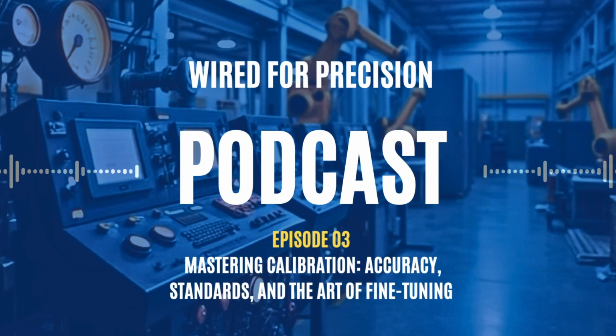Loop calibrators. These are designed specifically for current loops, often used in analog process signals, 4 to 20 milliamps. They can simulate, source, and measure loop current, making them indispensable for control loops. Each method depends on what you're calibrating. For example, if you're working on a flow meter, you might use a reference meter or a prover. For a load cell, you'll need certified test weights. It's about matching the right tool to the device and the environment you're in.